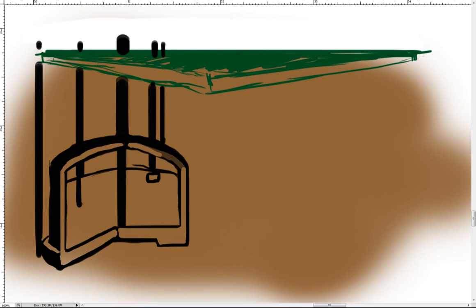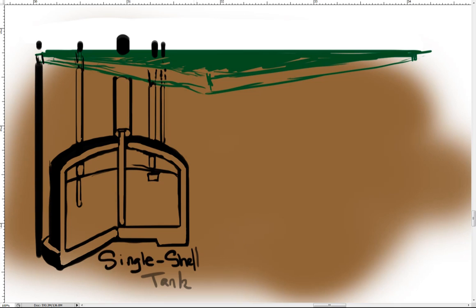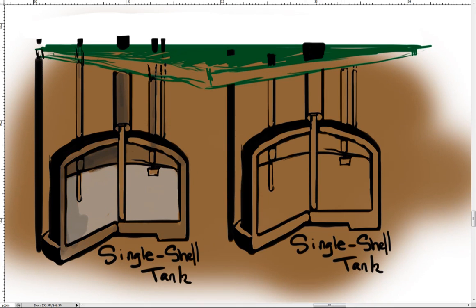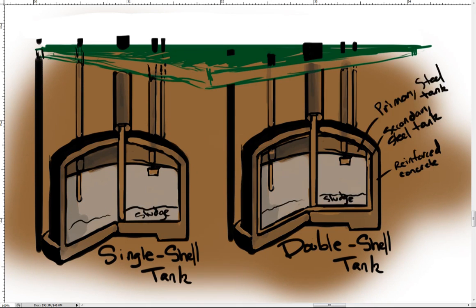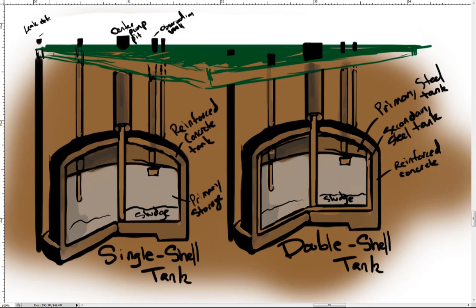There are two kinds: single-shell and double-shell. Single-shell tanks are holding bins made of carbon steel surrounded by reinforced concrete and buried underground. Double-shell tanks have a second shell of carbon steel surrounding the concrete and carbon steel and are equipped with leak detection systems.